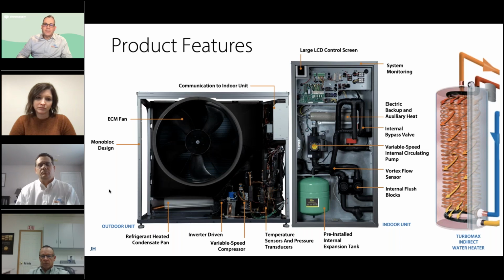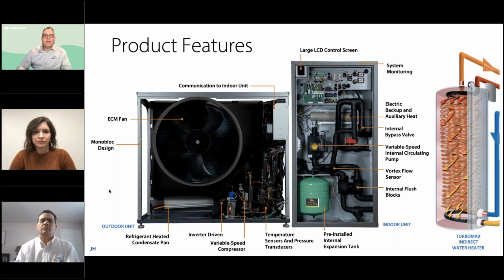On the far right is the indirect water heater. This is a special water heater that we've been using for quite a while with heat pumps, so that it's not new to the air to water technology. As you can see, that big copper coil inside the indirect is unique because it's not like a typical boiler indirect water heater where the boiler water goes through the heat exchanger. In this case, the load water from the heat pump is the storage portion of the water heater, and the potable water actually goes through that copper heat exchanger. So it's more like an indirect water heater. That gives us some advantages in that we can use lower water temperatures, which we would be able to provide from the heat pump, although it can do up to 135-degree water, so it's not that low in that regard. But it's also our storage tank when we go into defrost mode.